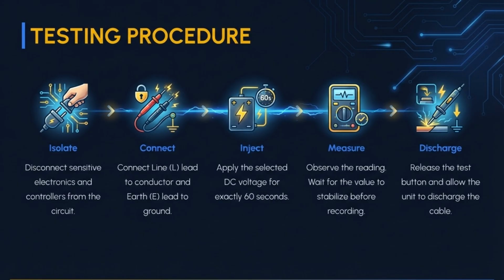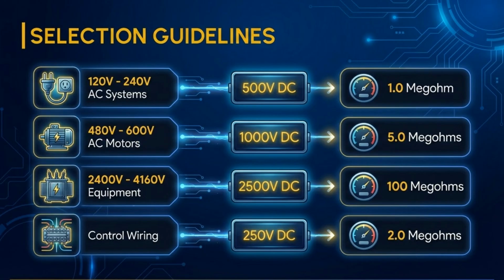The testing procedure involves 5 steps. Isolate sensitive electronics, connect the leads, inject the selected DC voltage for 60 seconds, measure the stabilized reading, and finally, discharge the cable. Follow these selection guidelines for testing.